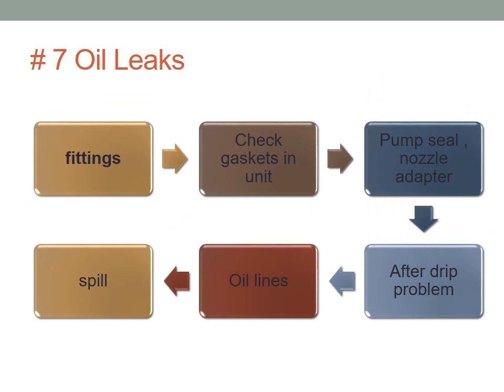Oil leaks, check for fittings, replace gaskets. Also nozzles and seal. Usually if you've done the oil line correctly, it should not leak. If it leaks, there's something wrong with the fitting. Somebody probably stepped on it. And after-drip problems: something happens inside the boiler where you have after-dripping, and the dripping comes out of the boiler's body and leaks underneath the boiler. Again, check the oil lines, and also check for spills when the tank was filled.